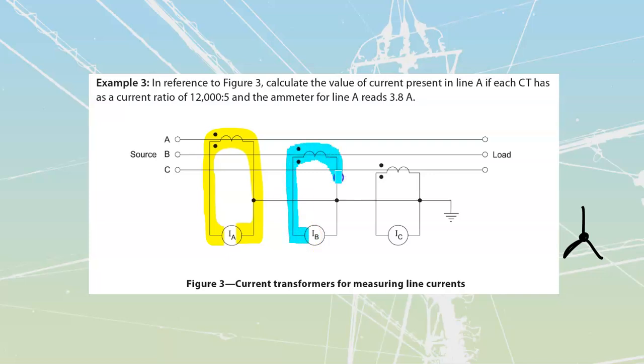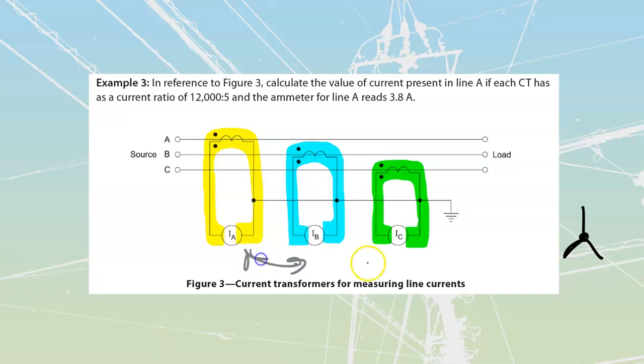The CT itself is reading that loop with the ammeter, and the ammeter is reading the CT with the loop. There is no complete path for voltage to go from this guy to that guy and all the way back and forth. So we never have anything where something from here goes up through here and then travels over, because ultimately we don't have more than one point connected on each, so there would never be any return path. So just know that we connect them in Y. This is for safety, and so that we have everything tied to a central neutral point. But we're still reading just the individual current.